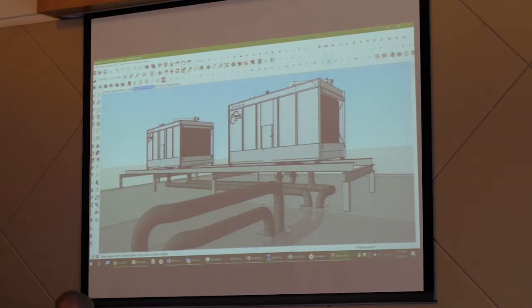Relative accuracy is one. Two sensors meeting an accuracy spec right out of the box could be off, dependent on the accuracy spec, 1 or 2 degrees, right? So the two sensors could think they're making the same temperature and have the tower fans making the water colder than the bypass valve's trying to make it, and so you're simultaneously heating and cooling. You can solve that problem by doing what's called relative calibration. You pick one sensor and say, that's my main sensor, calibrate the other one to it.